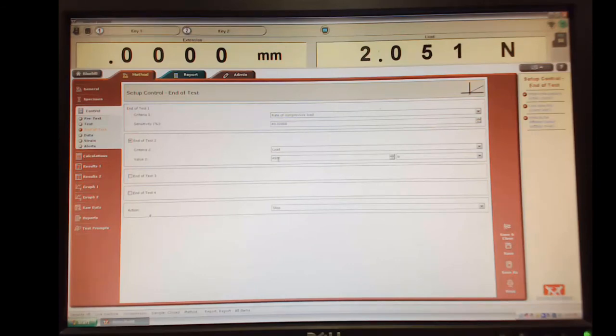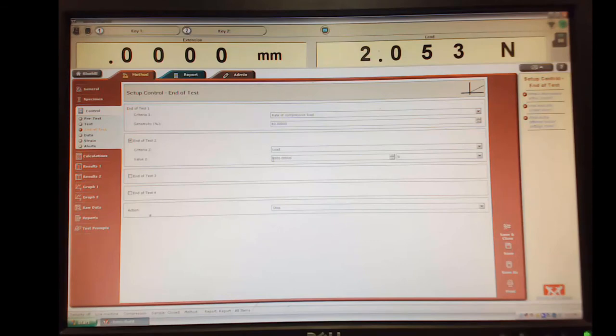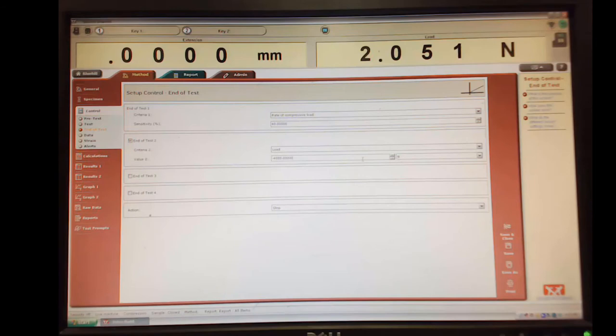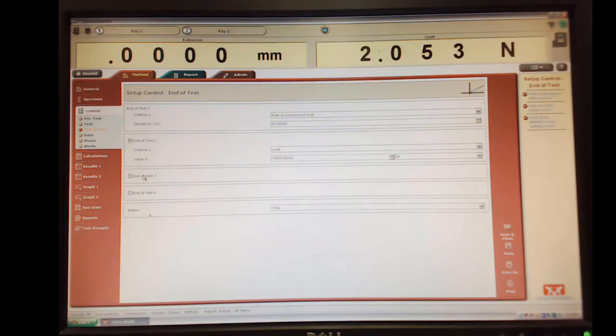Now, this is compression. If you remember, I did a little test on the tension, and so positive was a tension load. And so negative is going to be a compression load on here. So if I say, if we reach negative 4,000 newtons, we want to stop the test.